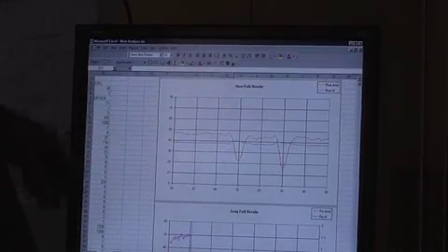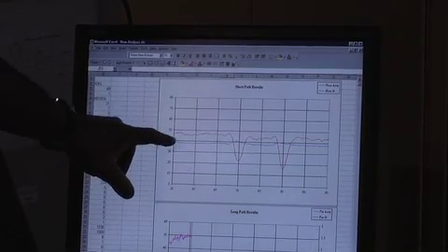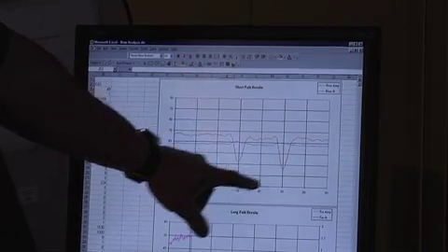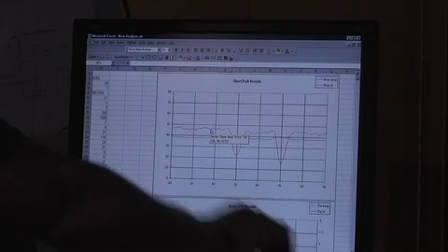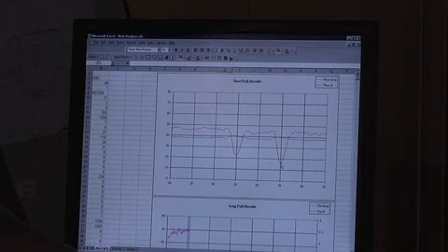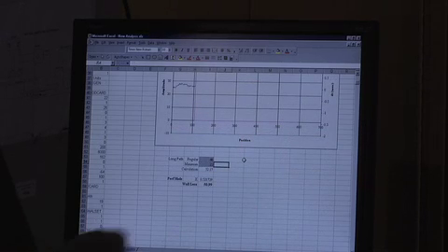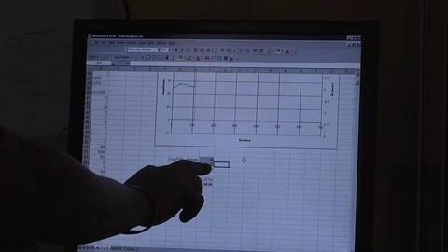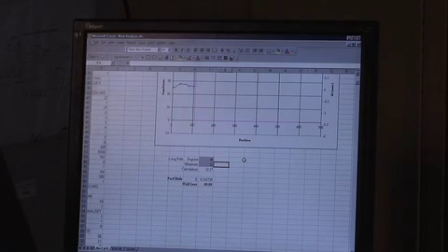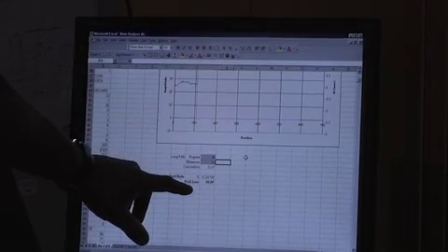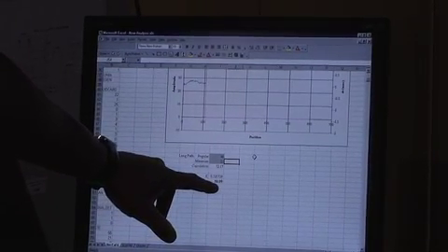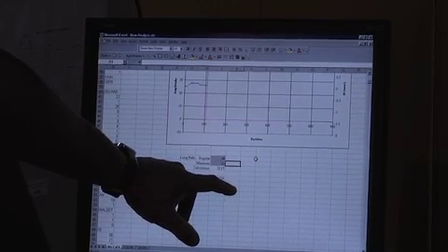This algorithm takes your data from both your RF raw data images and your real-time collection images, and it takes it to scale. And you can see your defects, your 75% flaw and your 50% flaw. So we could take a baseline reading and then come down to the lowest peak. Type in your baseline here and your lowest reading, and the algorithm does the calculation for you. As you can see right here, the estimated wall loss is 50.99% volume loss.